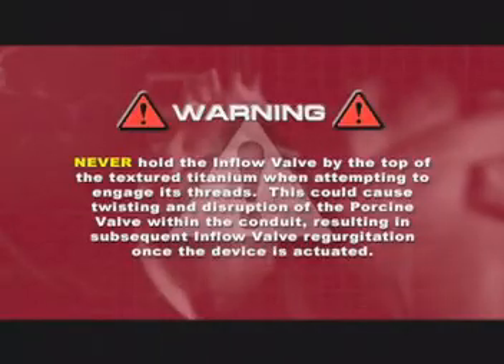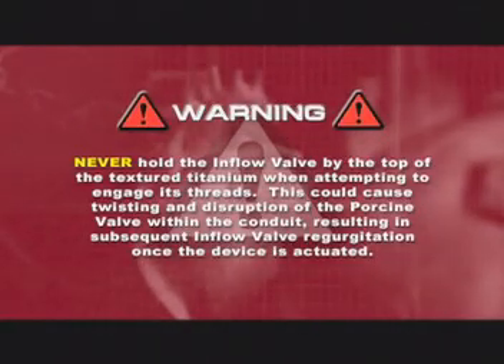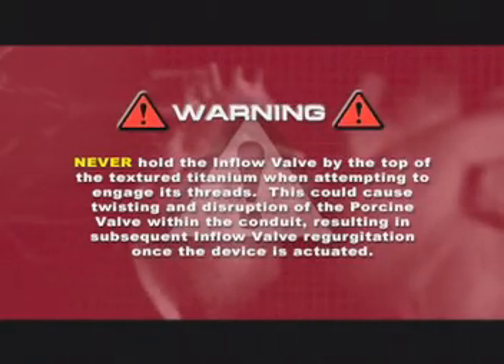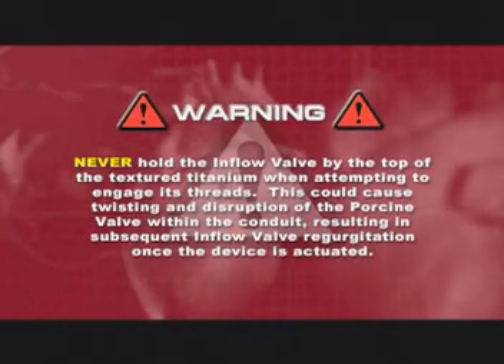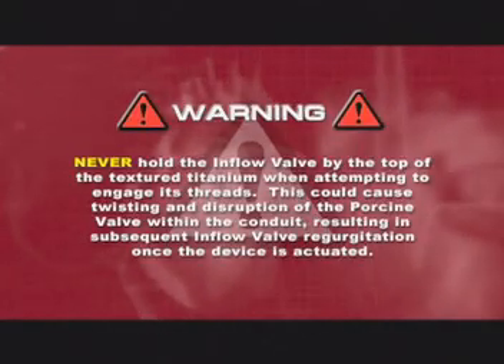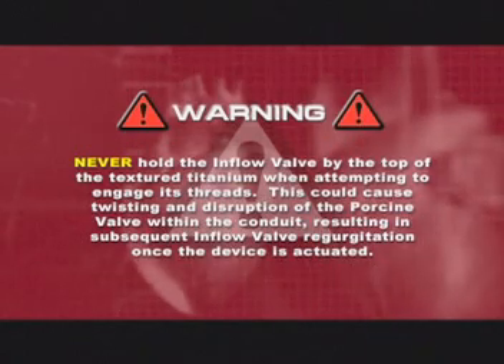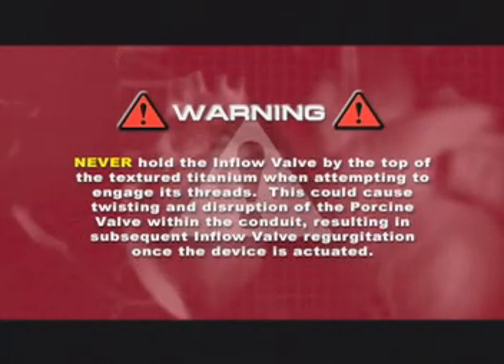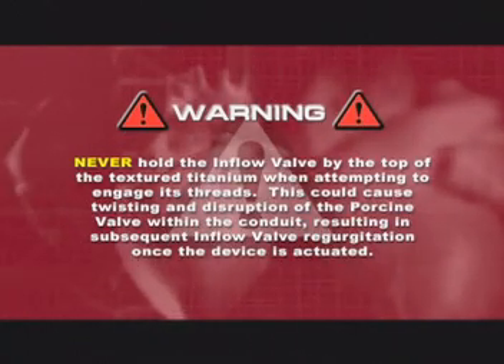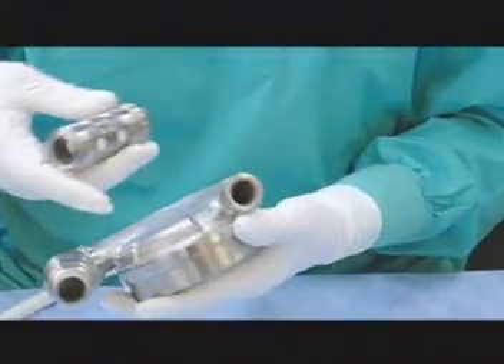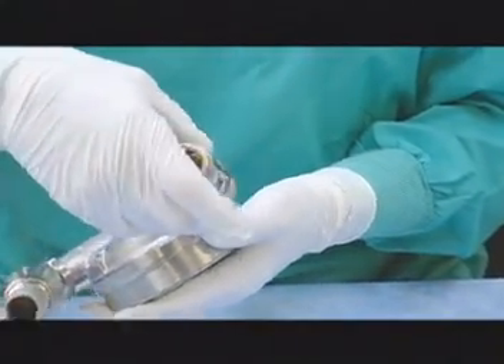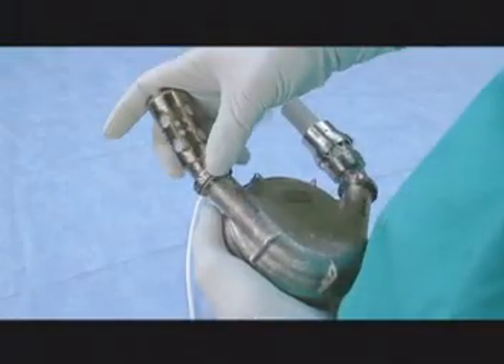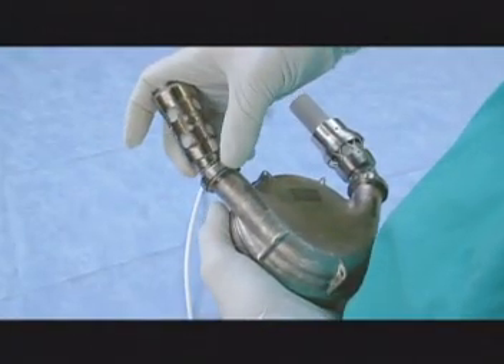Warning: never hold the inflow valve by the top of the textured titanium when attempting to engage its threads. This could cause twisting and disruption of the porcine valve within the conduit, resulting in subsequent inflow valve regurgitation once the device is actuated. Next, apply the outflow valve conduit to the outflow side of the pump, the left side when the anterior side is facing you.